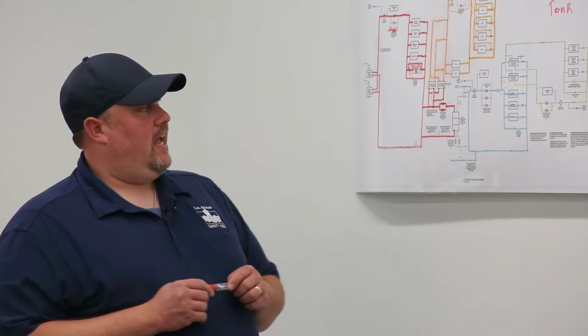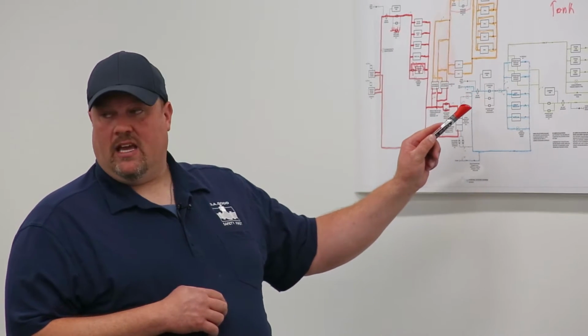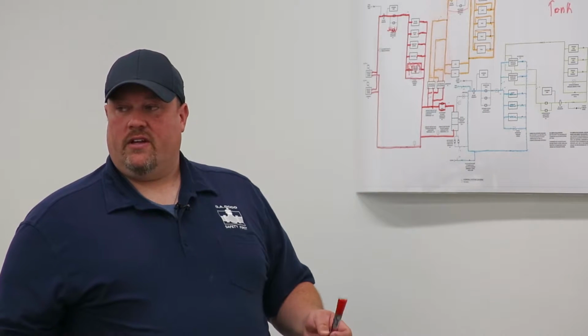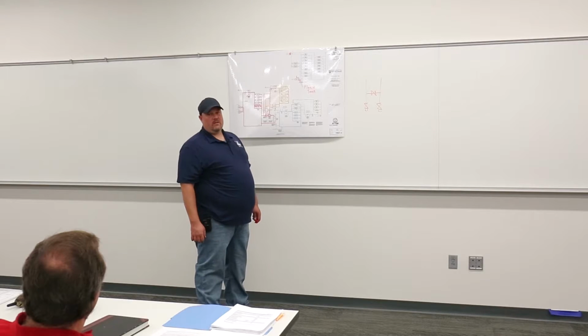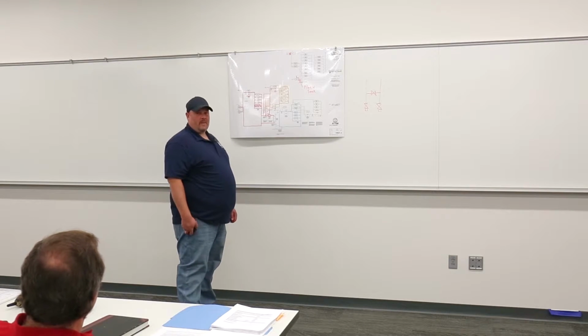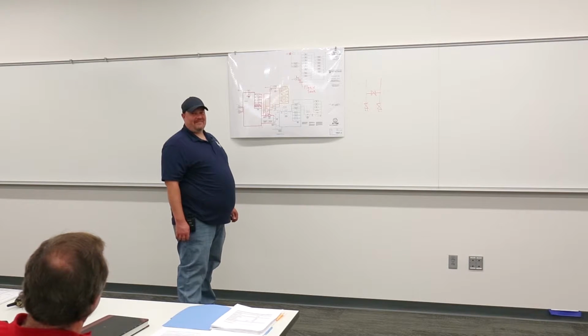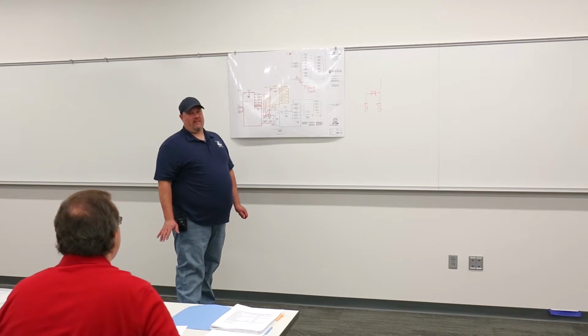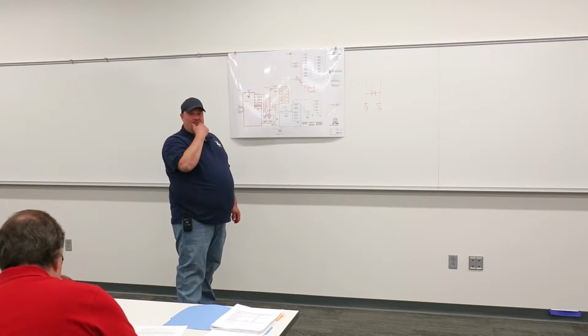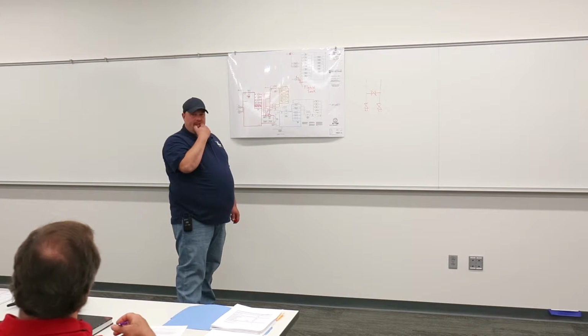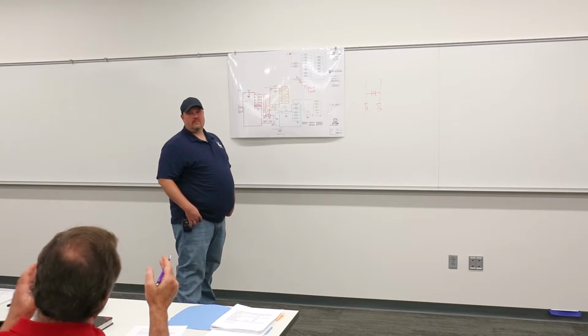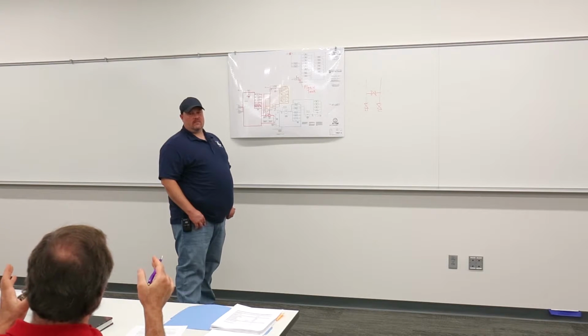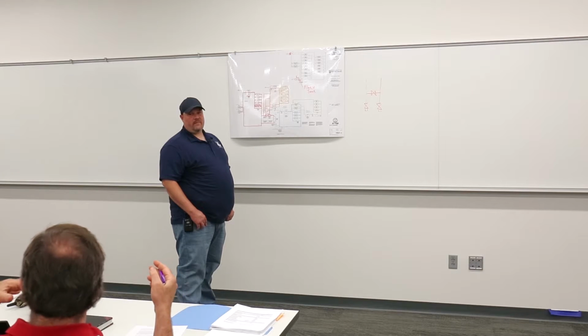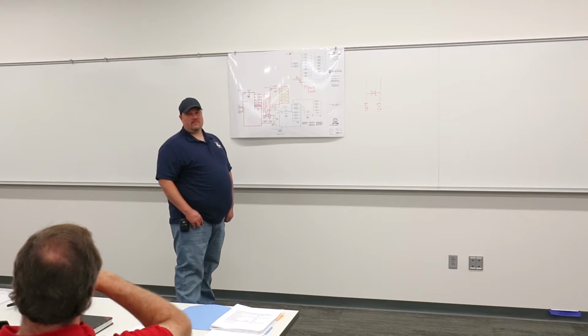And it also has a system makeup water feed in case that were to ever be completely closed off, as it would, if we happen to lose water somewhere, it would make up its own water as well, just as if it was a closed loop on its own. Okay. Well, we won't address that at the moment, but we will address what we need to talk about. It's easily valved off. I think the makeup is okay, but what we have to be careful of is the expansion tank because it can become the expansion tank for the whole site. In other words, if it's set higher, it can force the system up and this whole system can kind of float around.